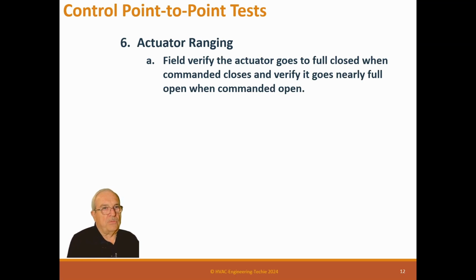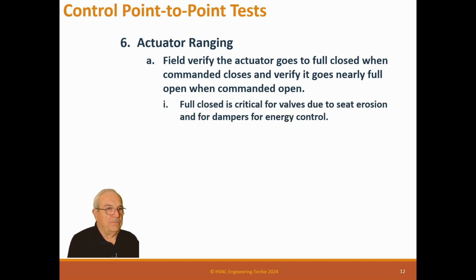Actuator ranging. Field verify the actuator goes to full closed when commanded closed, and verify it goes nearly full open when commanded open. Again, full open really is not a problem. Full close is critical for valves due to seat erosion and for dampers and energy control. So if you have a steam valve, and the higher the pressure, the more critical this gets. If that valve goes full close but actually stays open at 0.5%, it will destroy the valve. The steam will actually erode the seat in a very short period of time. So you need to make sure that the valves go full close.